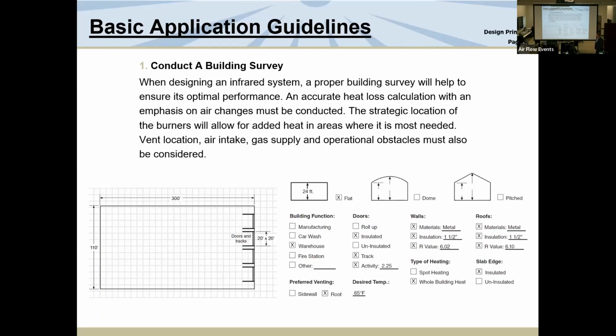And I can tell you, when we do a survey, if I'm on the phone, I use a rule of 50. If the building's insulated, for me to get talking points, I multiply their square footage times 50. That gives me an idea of how many BTUs need to go in that space. If I've got a 1 gallon bucket in front of me, I need to pour 1 gallon of water in it to fill it, right? Anything short, it's not full. Anything more, it's too much. So we look at what the supply is, and I can tell you, for the sake of qualifying a customer, 50 BTUs per square foot is good.